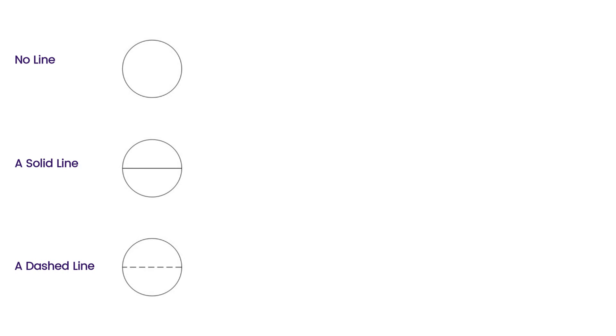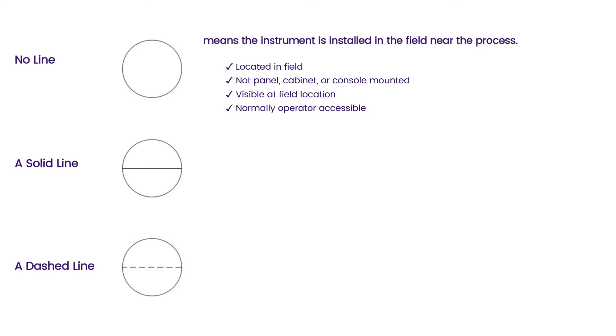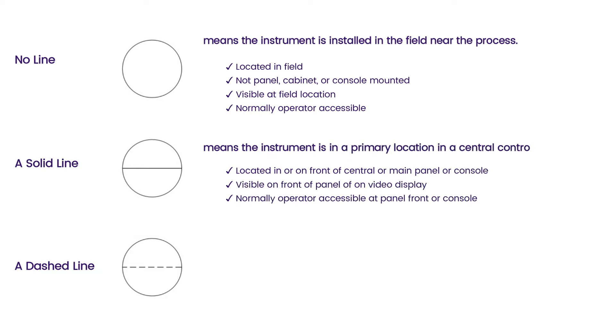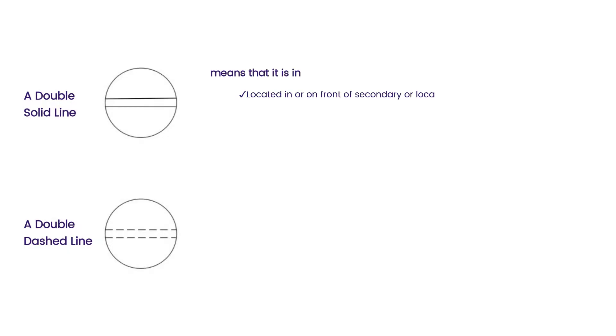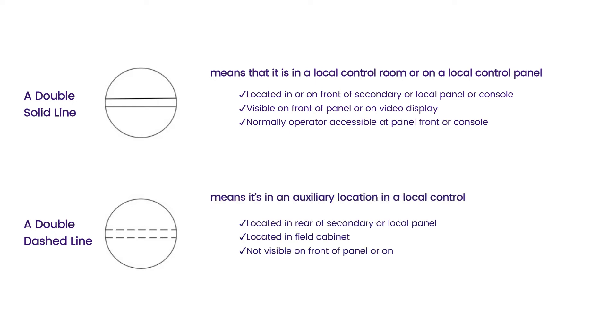In instrument indication symbols, lines can be different as per instrument location. No line means the instrument is installed in the field near the process. A solid line means the instrument is in a primary location in a central control room. A dashed line tells us that the instrument is in an auxiliary location in a central control room. A double solid line means that it is in a local control room or on a local control panel. A double dashed line means it's in an auxiliary location in a local control room or local control panel.